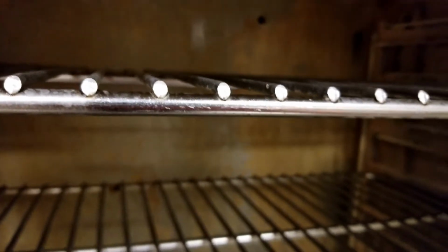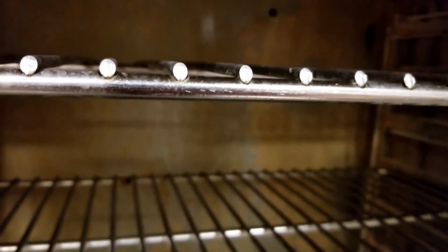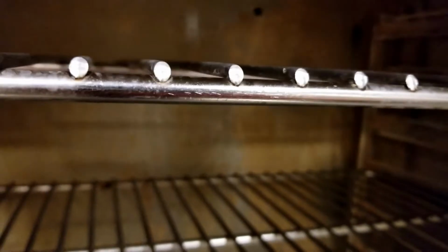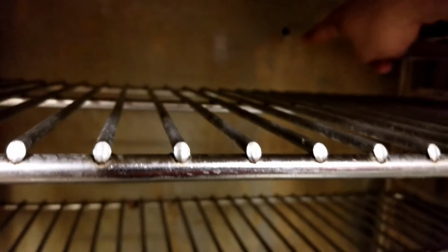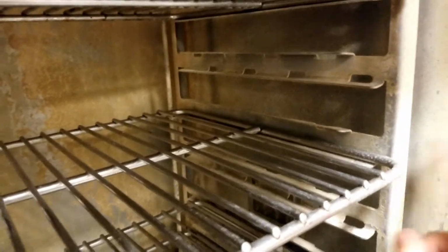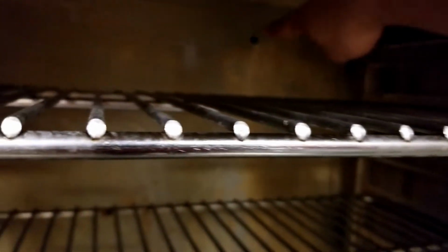If that hole is clogged up, it'll constantly heat because it keeps trying to produce steam, and it's going to keep spraying water and billowing a lot of steam. Just stick something in there and clear it out — you'll see it's got a lot of calcium buildup. Clear that hole out, and that usually will take care of the problem.